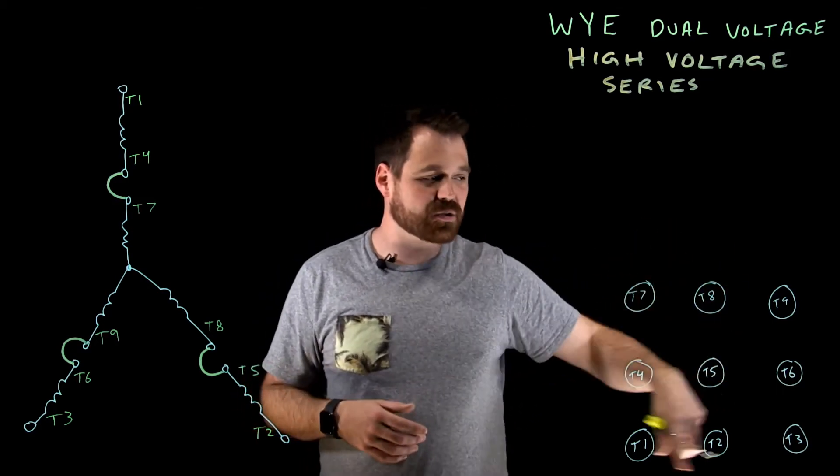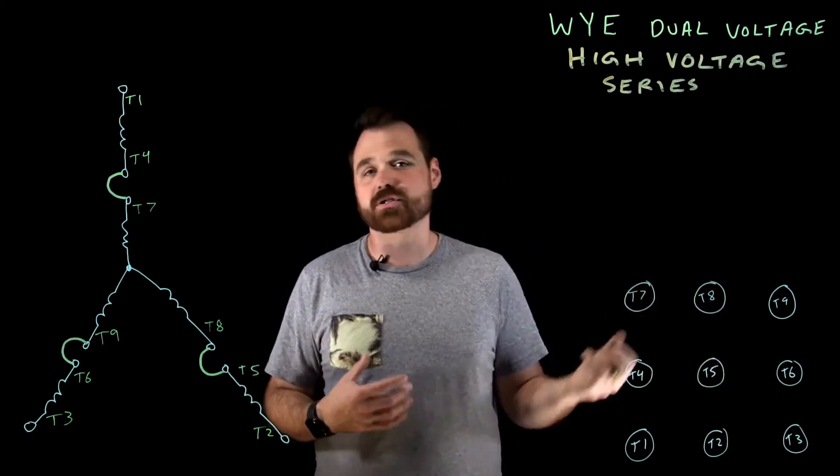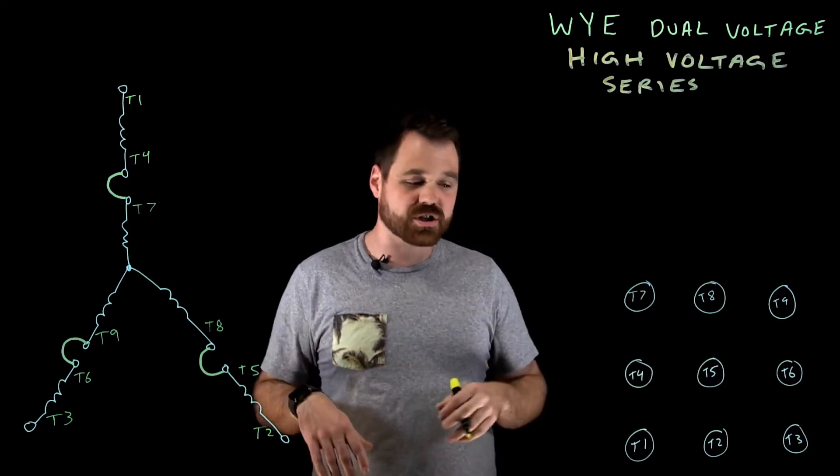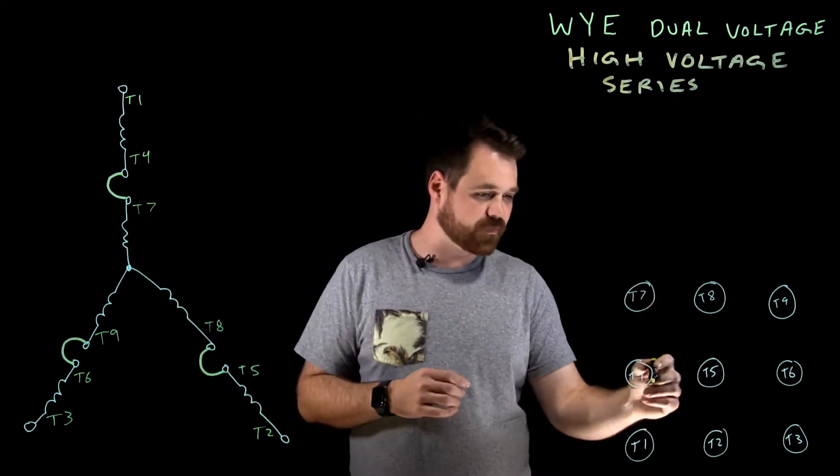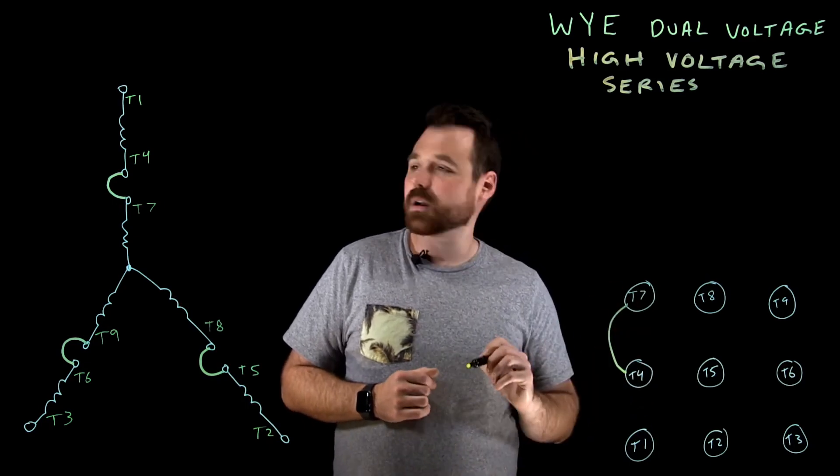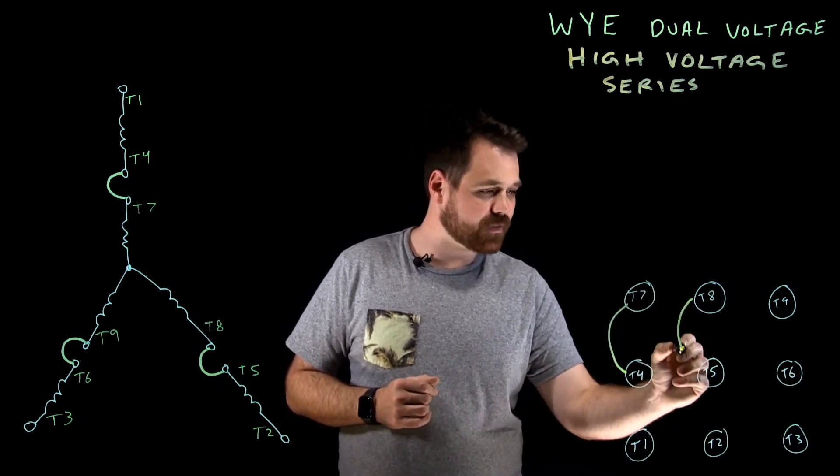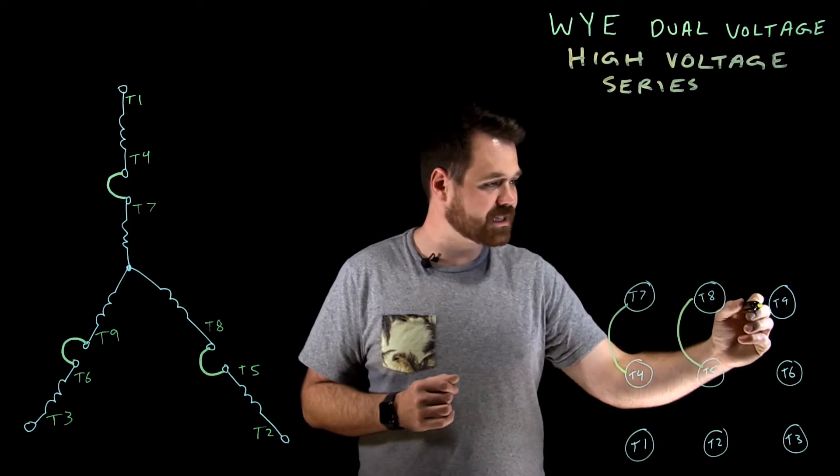And then what I have over here, these would just represent my nine conductors coming out of my junction box. And I would just make those connections over here so I can help visualize it. So T4 to T7, T8 to T5, T6 to T9.